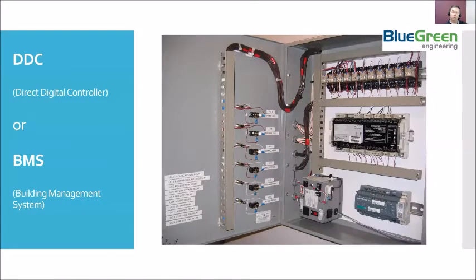These are the smart controllers. The simplest form is the direct digital controller, where a bit of smart hardware sits in the switchboard, and it takes inputs from various sources like temperatures or occupancy, and it adjusts the performance of the system accordingly. So if it's a very hot day, we could have the variable speed drive running at a maximum speed of 80%, whereas if it's a cooler day, we could, say, run it up to 70 or 75%.